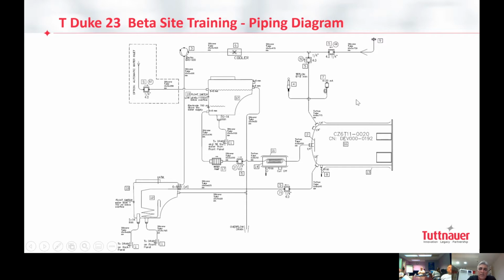Okay, and then the sterilization time started, counting the sterilization time. At the end of the sterilization, we open this valve because before we start with the vacuum for drying, we would like to get free of all the steam. Remember, right? All the pressure, all the steam gets released from the bottom, along with any condensation. The water comes from here, gets cold, condenses, and converts to water in the waste tank. Once we reach atmospheric pressure, a bit above, this one gets closed, and we start with the drying stage. Drying stage means vacuum. This one gets open, this, and this, and this.